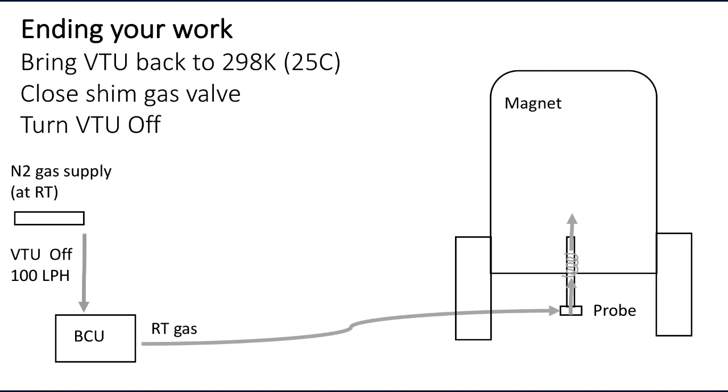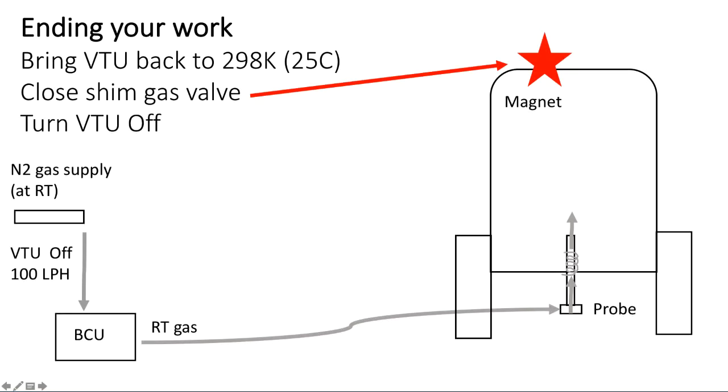After you brought spectrometer to 25 degrees C, your next step is to close the shim gas valve and then to turn off the VTU.